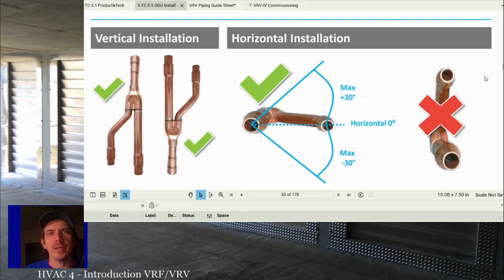Okay, so you're trying to get gravity to work with you on the movement of the refrigerant. That's the whole purpose of having the rules as far as how these things can be positioned. We tend to forget sometimes that refrigerant is this magic thing inside the system that we pipe to and from the indoor and outdoor unit. Refrigerant's a fluid, okay? So it's going to behave like a fluid. Anytime we're talking about any fluid, from refrigerant to air, they will all behave relatively similarly in most situations. So if the water wouldn't run through your piping evenly, then the refrigerant is probably not going to run through the piping evenly. So the best you can do to let gravity and the natural flow of things help you make sure that things split and go to where they need to go, the better off you are.